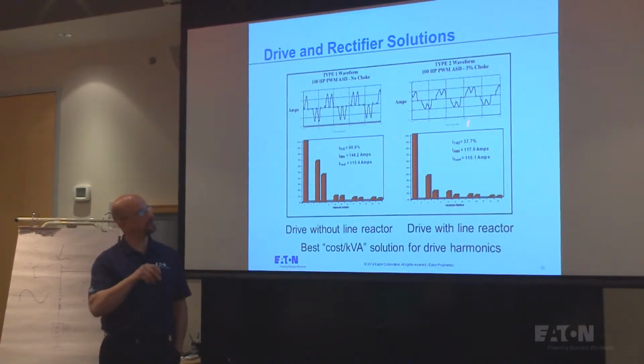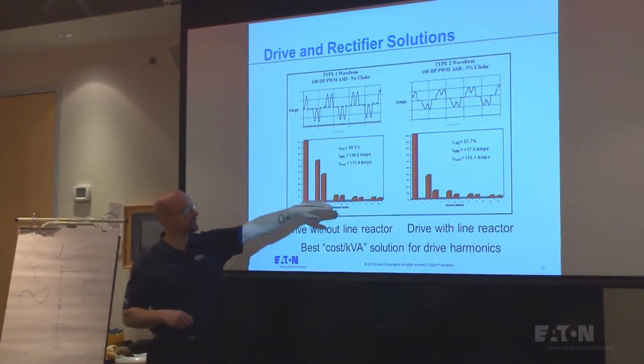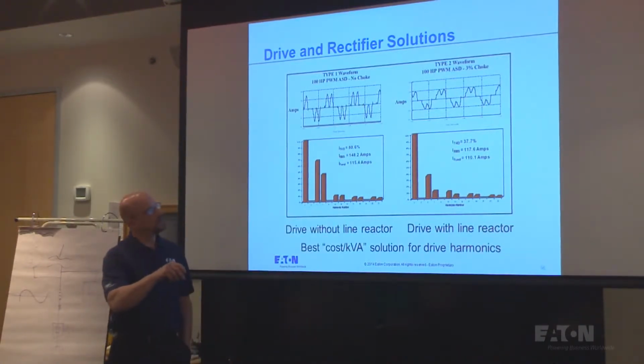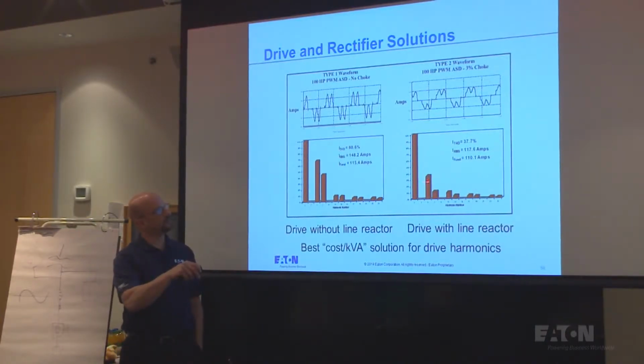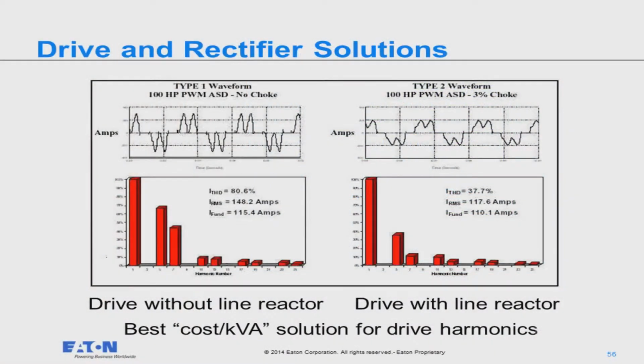And so what you end up with is, with a reactor in front of a drive, you reduce the harmonic current substantially. And as I mentioned, the harmonic currents go down as you go up in frequency. So the fifth harmonic here is significantly less over here than this one. Also, if you look at the RMS current, 148 amps, 117 amps, I did actually reduce my RMS current through the system as well.